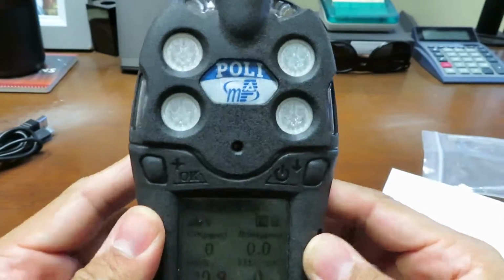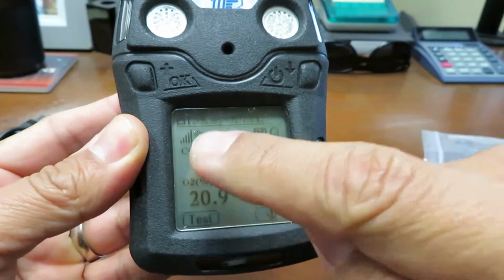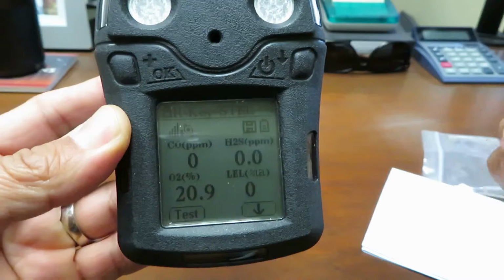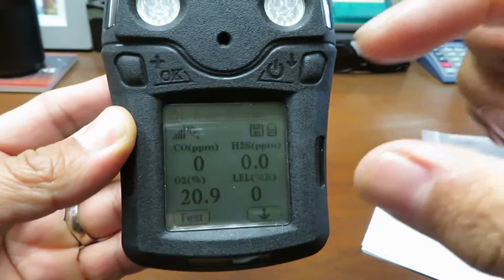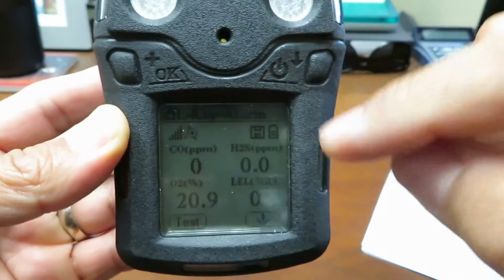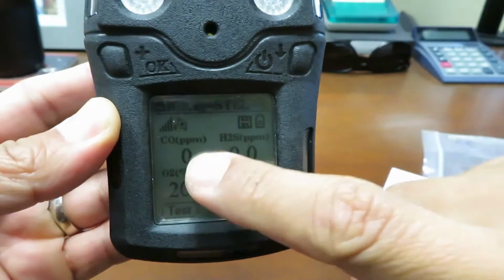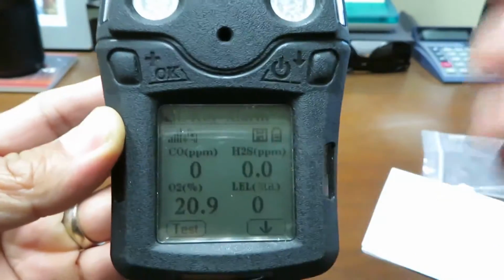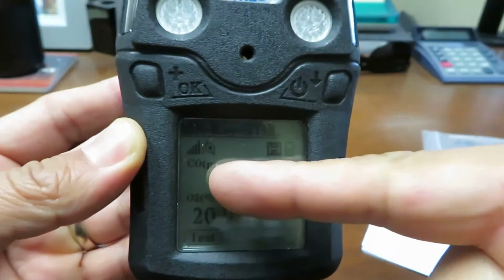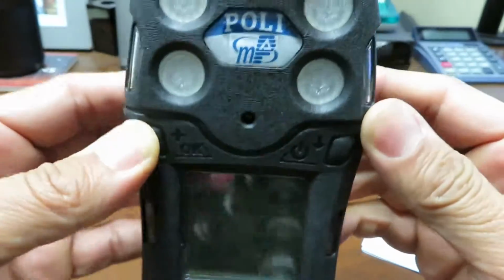These are intelligent sensors with a board on them, so when you put one into a slot, it knows what sensor is in what slot. It's a one-way operation, so you can't mess it up. If I were to put H2S in here instead of CO, it would recognize it as H2S. Back in the day, you'd have to install the sensor, go into the unit, select the socket, and tell it which sensor it was. These are smart sensors now.